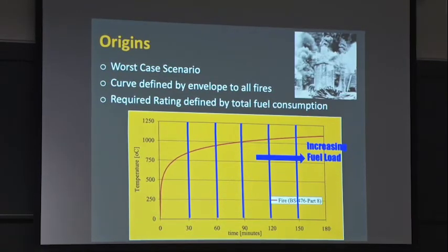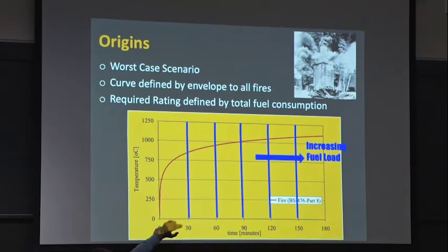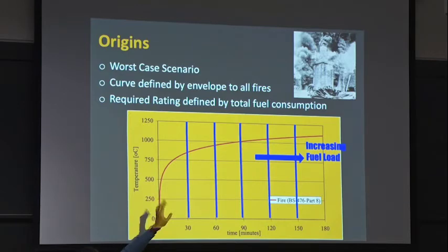Okay? So if I then test my structural element in such a way that it's exposed to the worst possible fire until time to burnout, and it still remains intact, then I can actually say that that structural element will never fail.